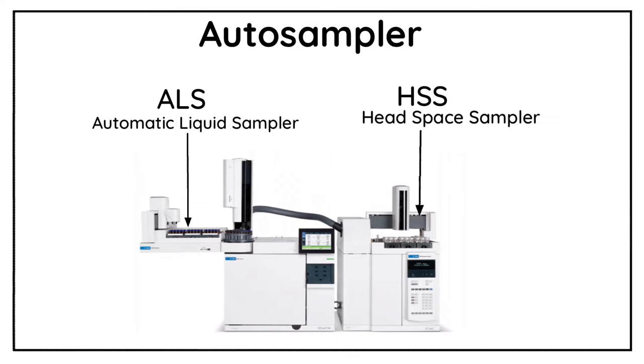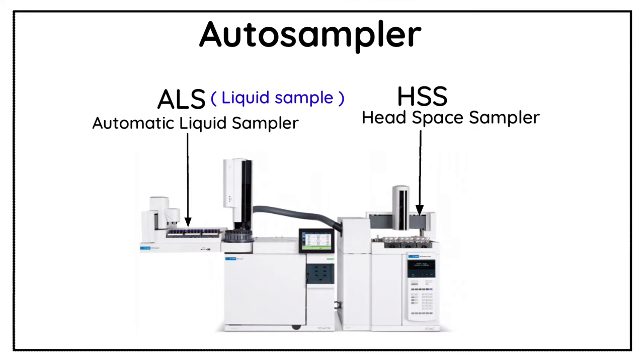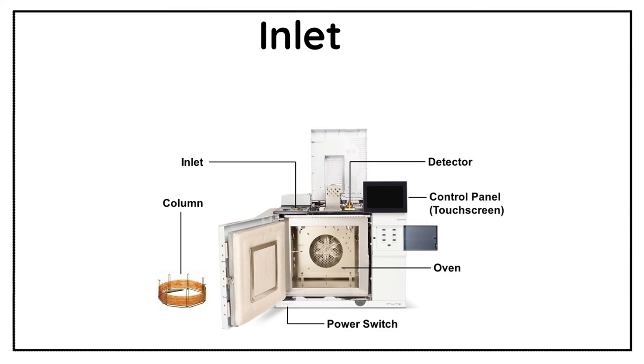The question arises: what is the difference between these two auto samplers? The answer is that when a sample is injected in liquid form then ALS is used, and when a sample is injected in vapor form then HSS is used. This is the basic difference between ALS and HSS which we should know.